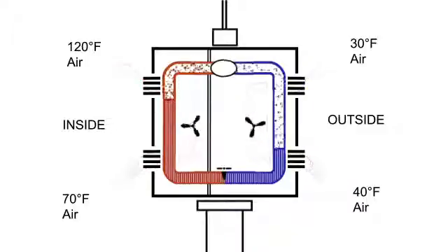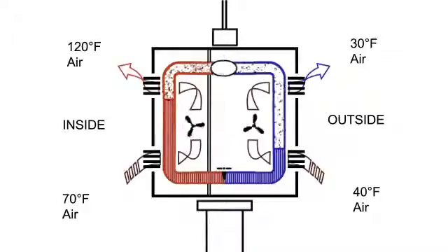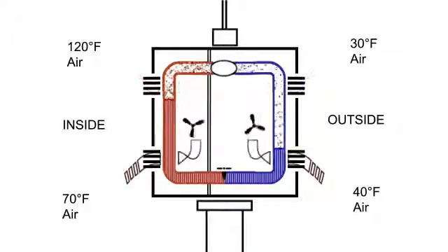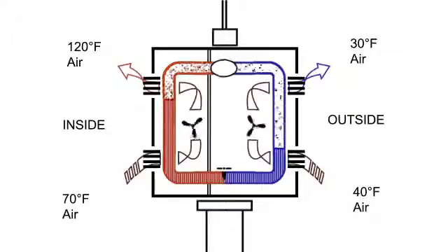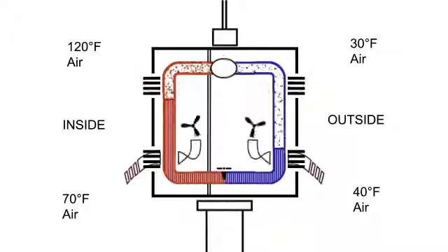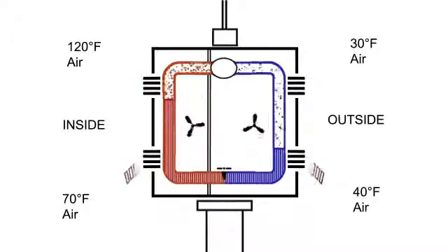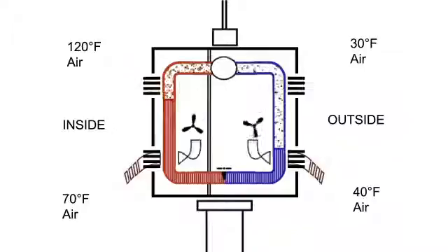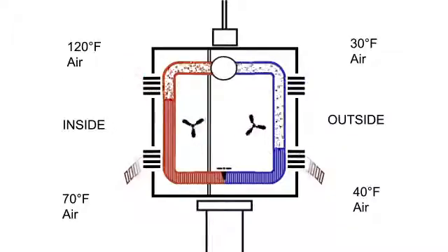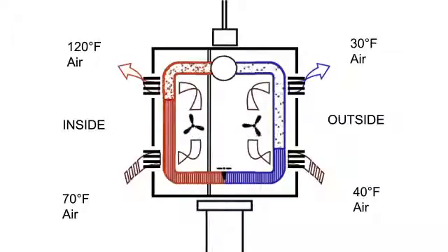By moving air over the condenser, which during the winter we find on the interior, recirculated room air may be warmed over the same coils that cool air in the summer. Note that in the wintertime condition, the heating mode, we are asking the coolant to evaporate in cold air. But when the air is very cold, fluid doesn't want to evaporate, and the compressor must work especially hard to create the appropriate pressure to force evaporation.